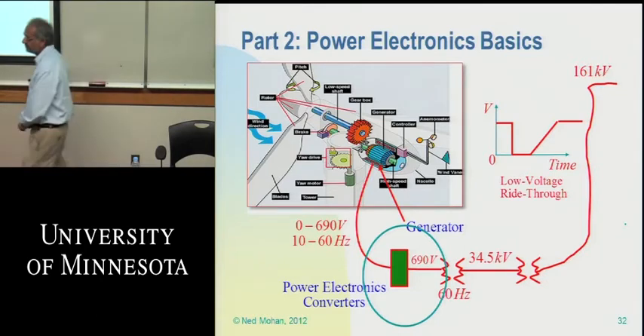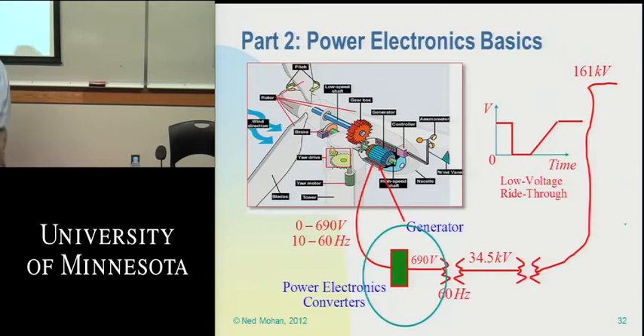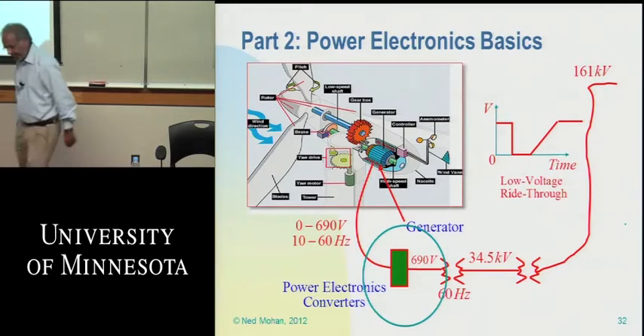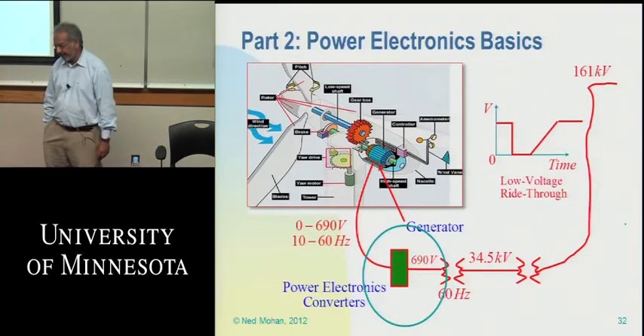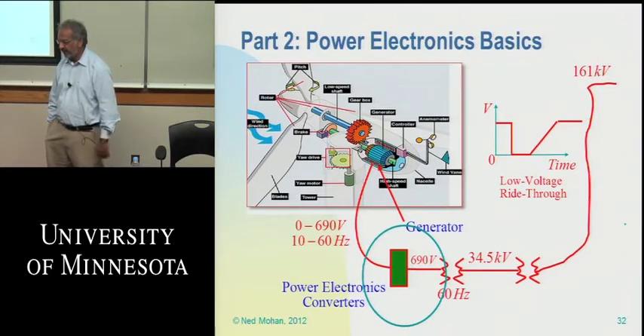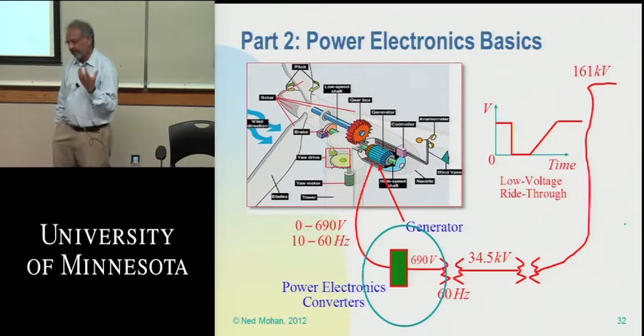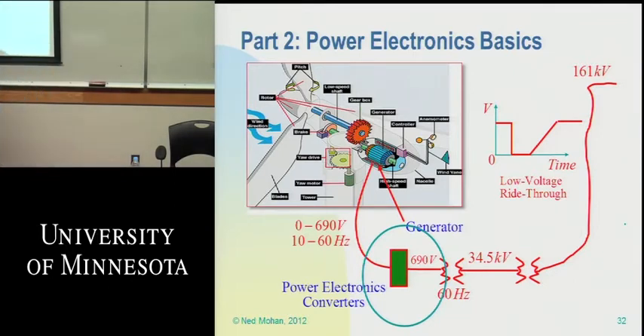As we increase the amount of renewables on the grid, does the amount of reactive power need to increase equally with that? Well, a lot of these systems can provide reactive power - that is a requirement, or at least a very desirable feature of these converters. That's true of wind turbines, and similarly photovoltaic inverters can also supply reactive power, so they can compensate for voltage drops by providing reactive power.